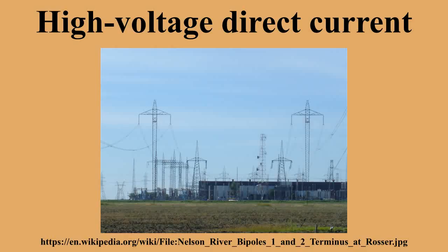Depending on voltage level and construction details, HVDC transmission losses are quoted as about 3.5% per 1,000 kilometers, which are 30 to 40% less than with AC lines at the same voltage levels. This is because direct current transfers only active power and thus causes lower losses than alternating current, which transfers both active and reactive power. HVDC transmission may also be selected for other technical benefits.